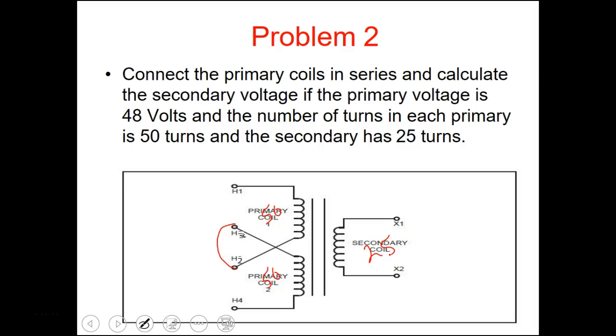And what would I get out of it? Yeah, so that would give me 30 volts. So these transformers, they'll give you one voltage. Normally the transformers don't give you the turns ratio, but they give you the voltages that it's set up for, where you can calculate the turns ratio and get anything you wanted to. So I could bring my input into the low side, take my output on the high side, and if I had it hooked for high voltage, I would get a multiply by 4, right? You understand? Or I could get a multiply by 2, depending on where I go.